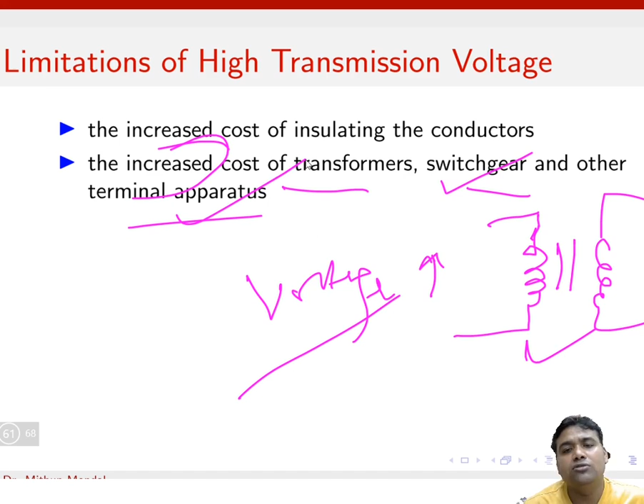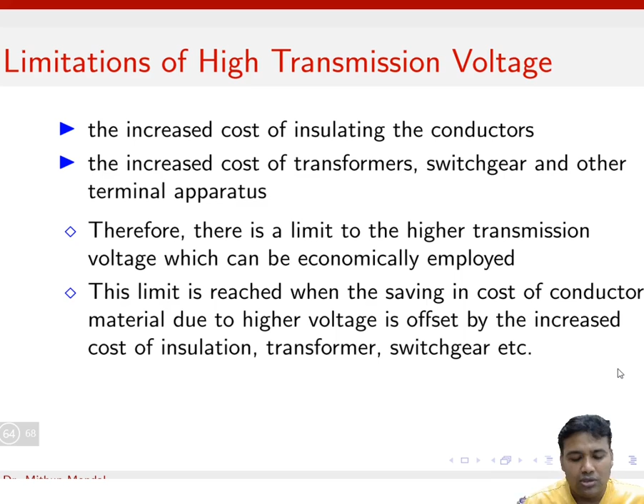Third, these limitations will limit the higher transmission voltage, so that we can economically transmit the power. We have to decide till what level of voltage we can increase so that we get maximum benefit of transmitting the power economically. There is a limit which is reached when the cost saving in conductor material due to higher voltage is offset by the increased cost of insulation, transformer and switchgear. Here we have discussed the increased cost of insulation, transformer, switchgear, other terminal apparatus, and the advantage that there will be a saving in the cost of the conductor. Which one is more, when you are increasing the level of the transmission voltage, you have to decide. So proper choice of the transmission voltage is essential, and is a question of economics.